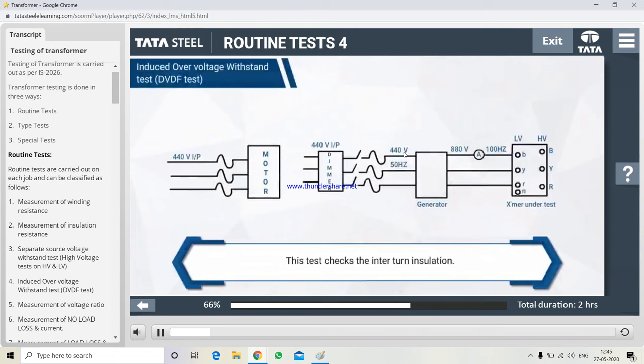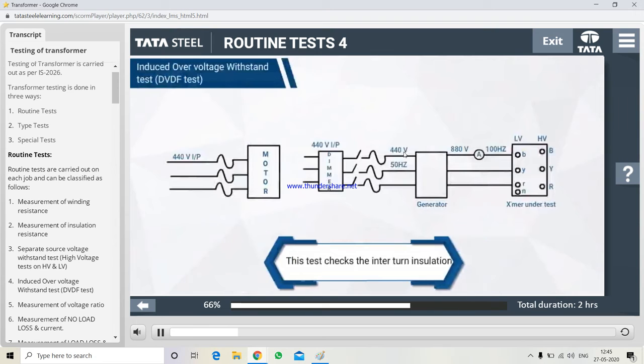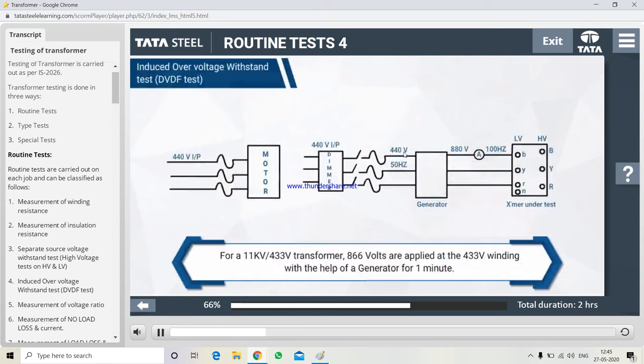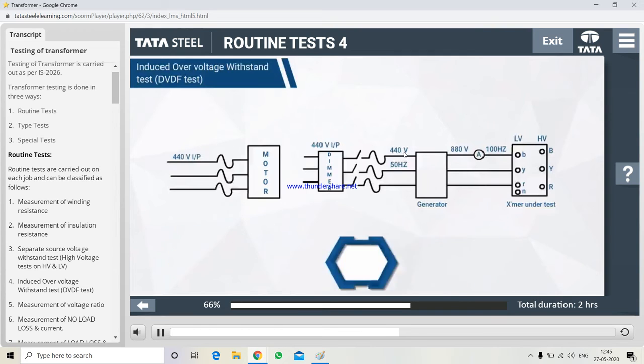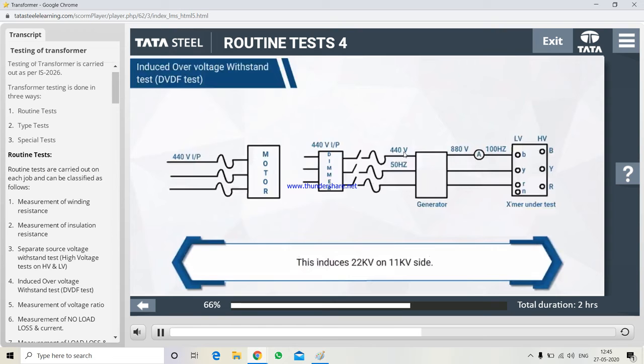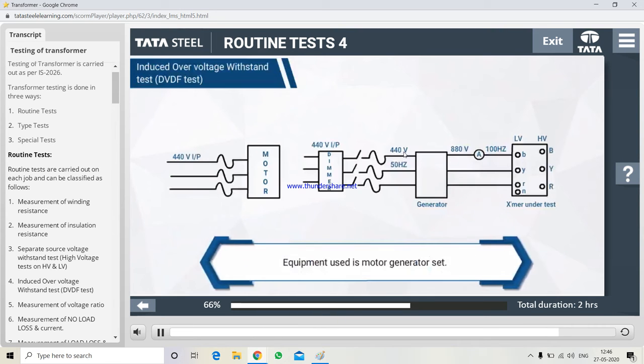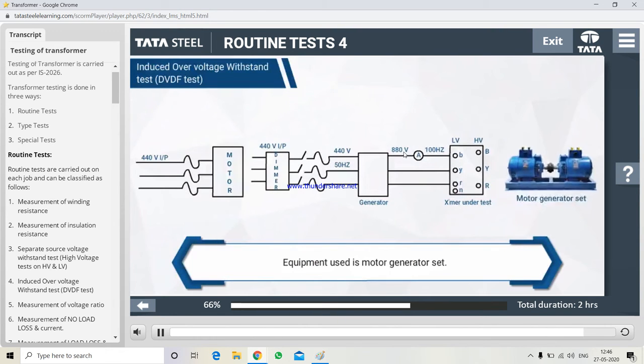This test checks the inter-turn insulation. For a 11 kV upon 433V transformer, 866 volts are applied at the 433V winding with the help of a generator for 1 minute. This induces 22 kV on 11 kV side. The frequency of the 866V supply is also increased to 100 Hz. Equipment used is motor generator set.